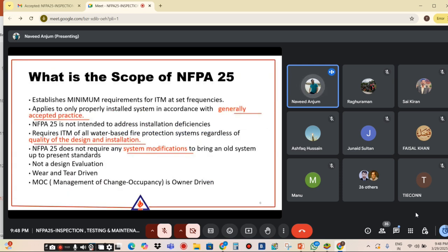So this is basically the scope of NFPA 25. If you are working as an inspector and you are going to visit a site for the inspection of a water-based system, you must know your scope. It is the scope of NFPA 25, which is mentioned in the administration part. Basically, it establishes the minimum requirements for ITM at set frequencies, applying only to properly installed systems in accordance with generally established practice. And NFPA 25 is not intended to address installation deficiencies.